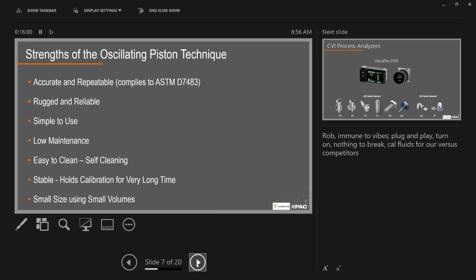Okay, so just to quickly review the strengths of our technology. So the accuracy, we're very accurate. We are 1% of the reading, and repeatability, we are 0.5%. We comply to ASTM method D7483, and we correlate to within 1% of other methods like ASTM D445. Regarding the ruggedness of the sensor, as Patrick explained, it's welded 316 stainless steel with copper coils in there, so there are no moving parts. If you drop it, if you hit it with a piece of equipment, there's nothing in there to break.